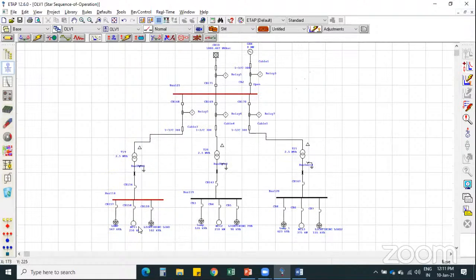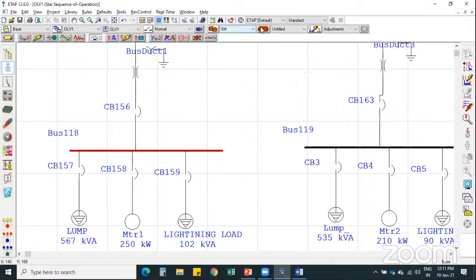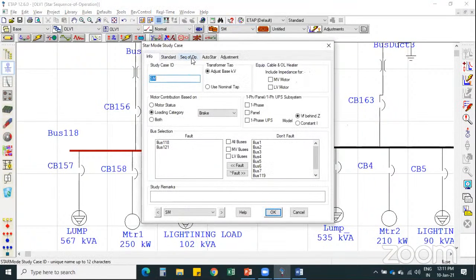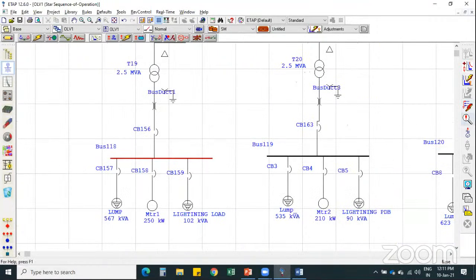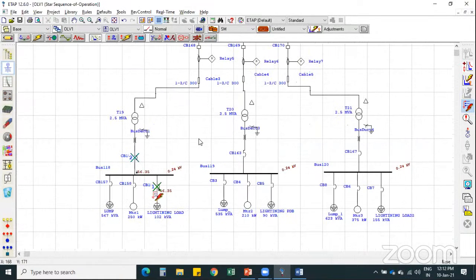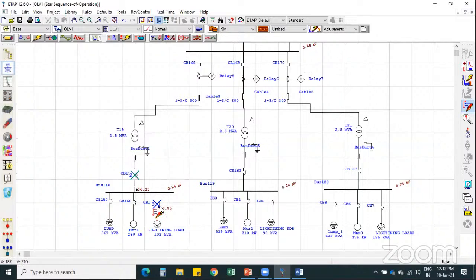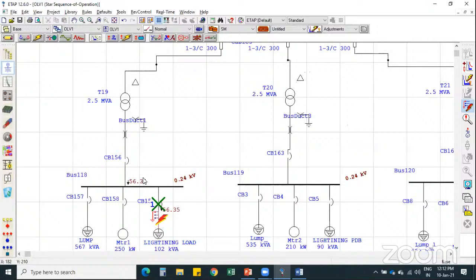Yes. Now see, for earth fault, as I have shown, in ETAP we can change the sequence of operation, meaning for what kind of fault we need to check whether the system is coordinated or not. So here there are the types of fault: three-phase fault, line to ground fault, line to line fault, and double line to ground fault option. For line to ground fault, let's select line to ground fault in ETAP. Now with the help of this fault insertion in ETAP, we can check the sequence of operation. Meaning if this fault occurs in any particular network, then the sequential operation will be in a similar way to what we have done. Now here you can see the operation: 1 here and 3 here.